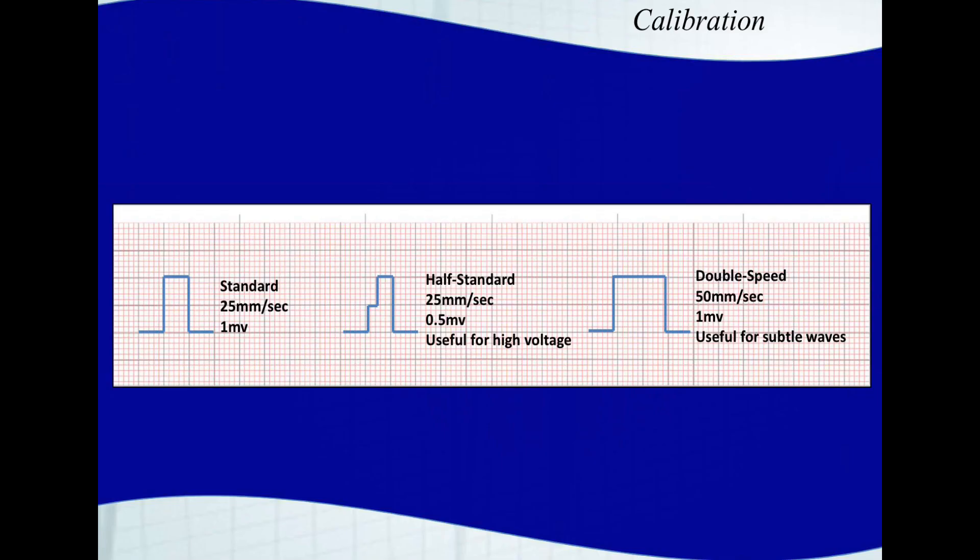Sometimes when an EKG prints out, it'll print a little calibration mark. Most American EKGs print with a one millivolt standard calibration at 25 millimeters per second print speed.